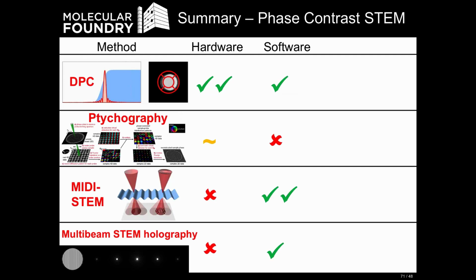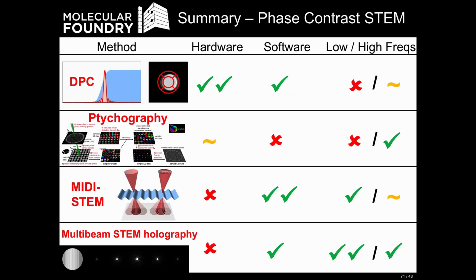For software reconstruction, DPC and MIDI-STEM are very easy to reconstruct. Ptychography is computationally expensive, and the multibeam method is also very easy to reconstruct—you just do an inverse Fourier transform. For signal recovery, ptychography wins for the high spatial frequencies. For the low spatial frequencies, the thickness signal, the phase-wrapped signal, that's where multibeam really wins out. MIDI is about halfway in between those two.